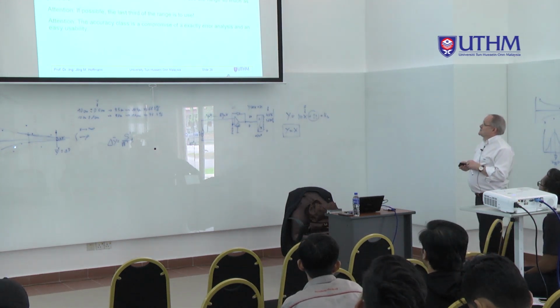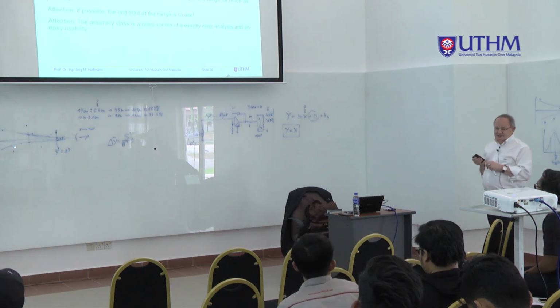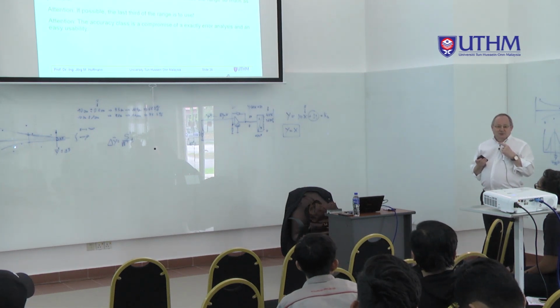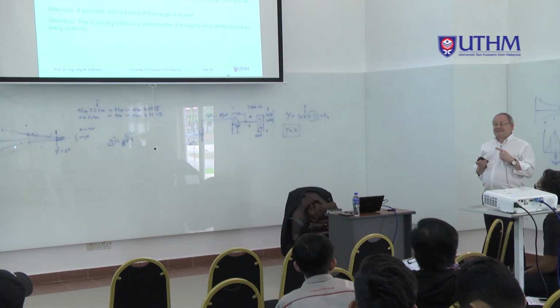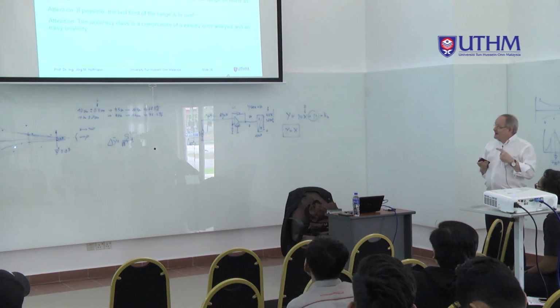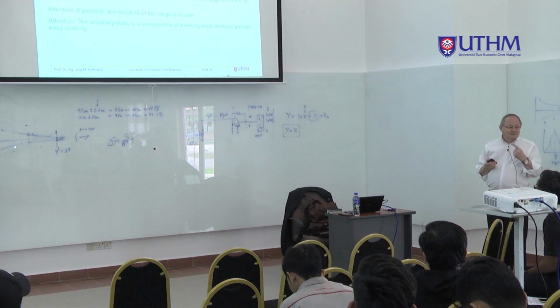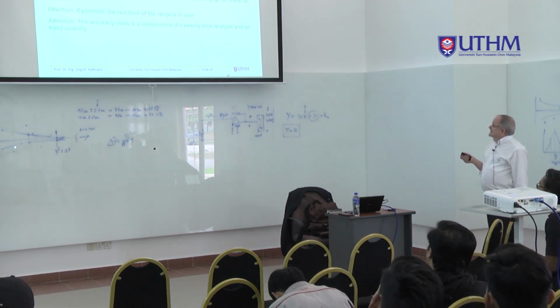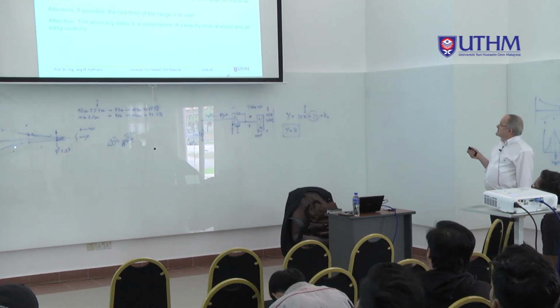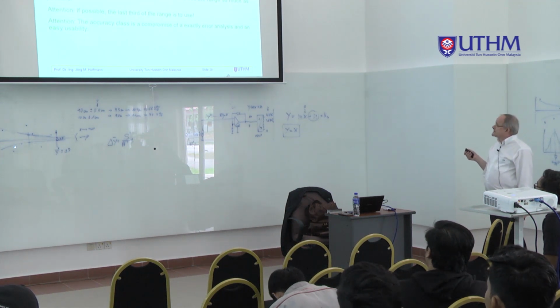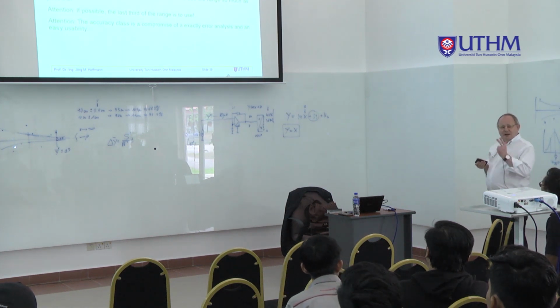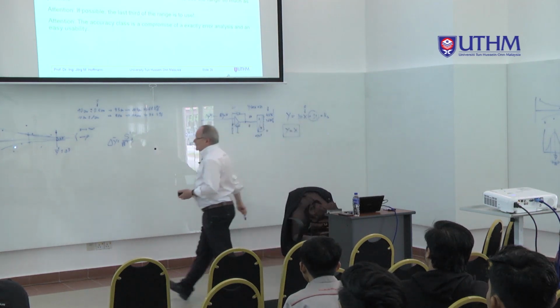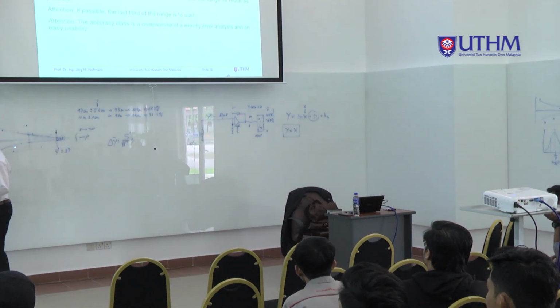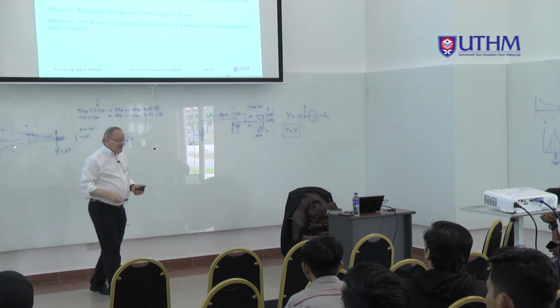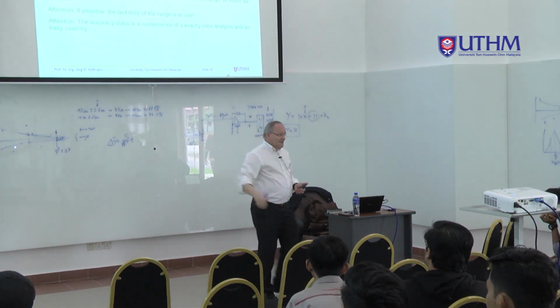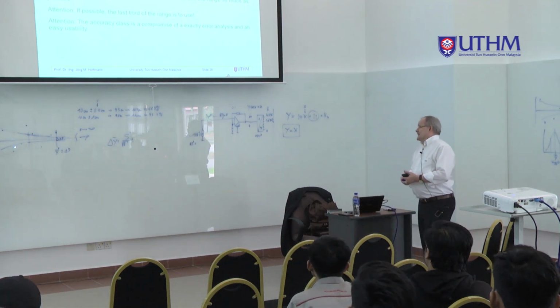And therefore, when you read about the so-called accuracy class, that is an additional method used many, many times by the industry, but it's not a scientific method. I will explain how it works. It is very easy, therefore the industry likes it. The accuracy class is the maximum expected error in percent of the measuring range. That means the companies say, never will you measure a bigger error. That is scientifically wrong, because the standard deviation goes from 0 to infinity. You can never say never. You can say 99.999%, but you can never say never. But the industry says never.